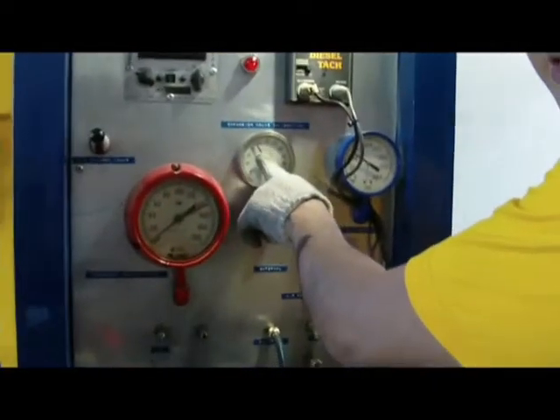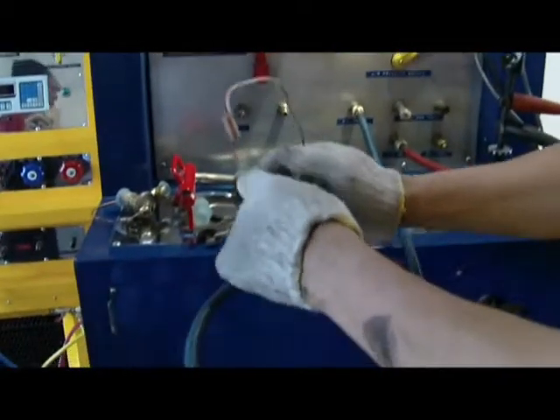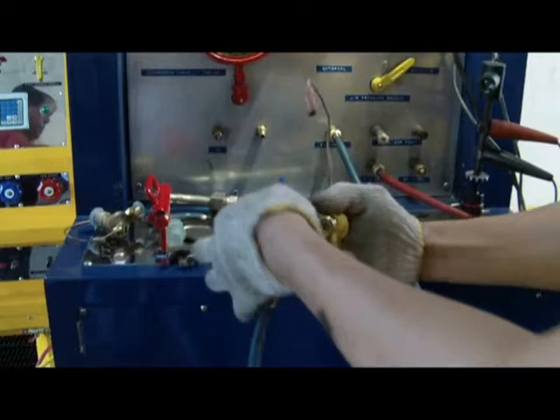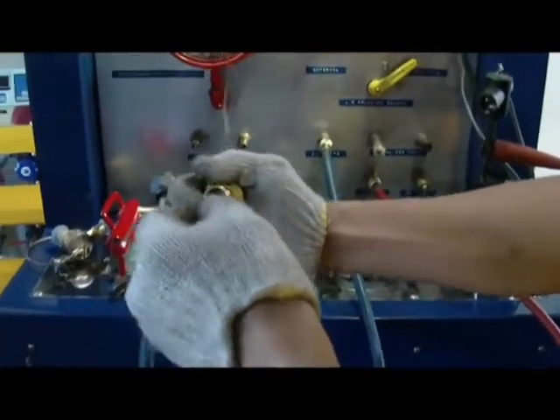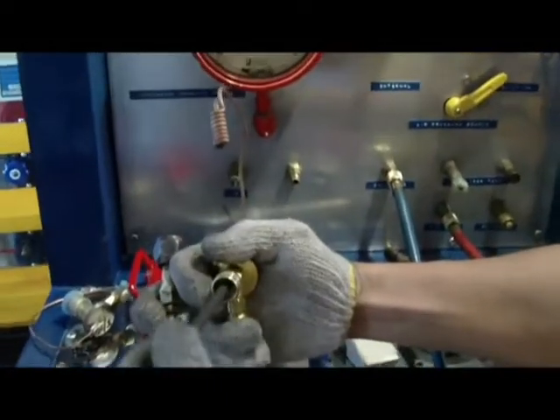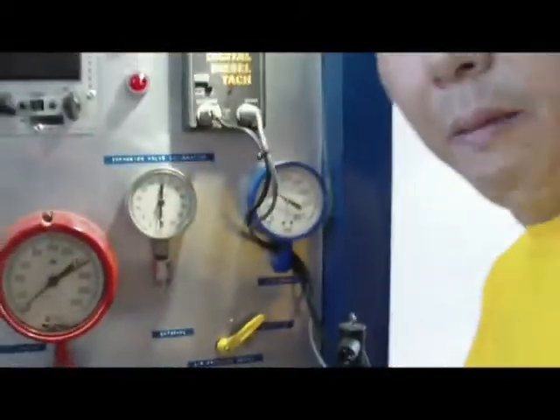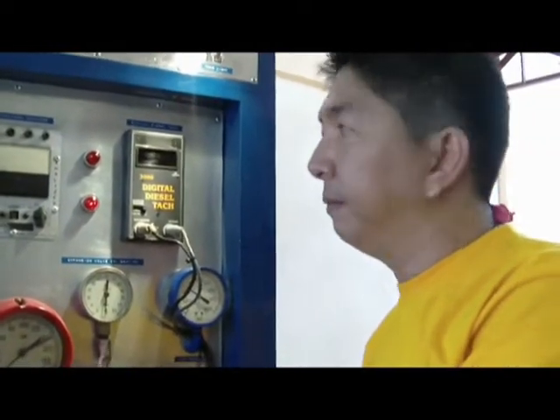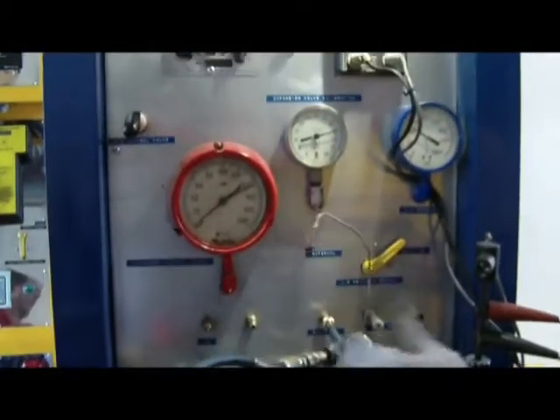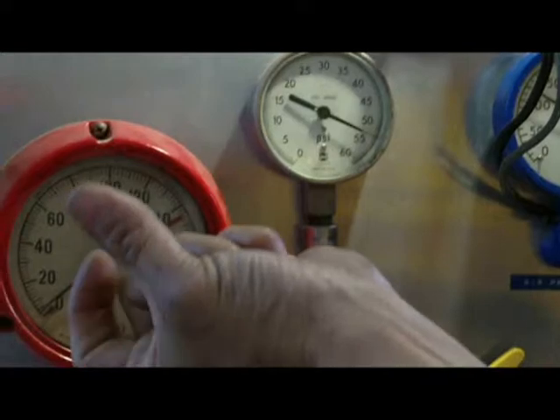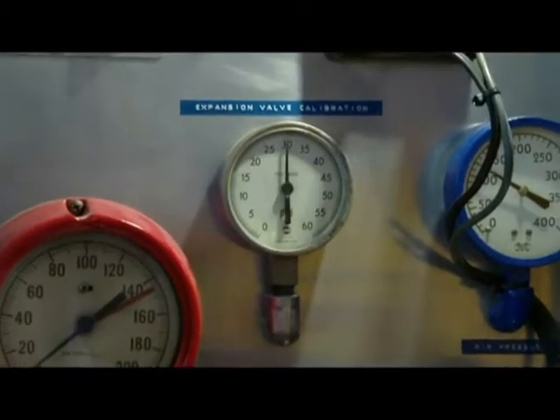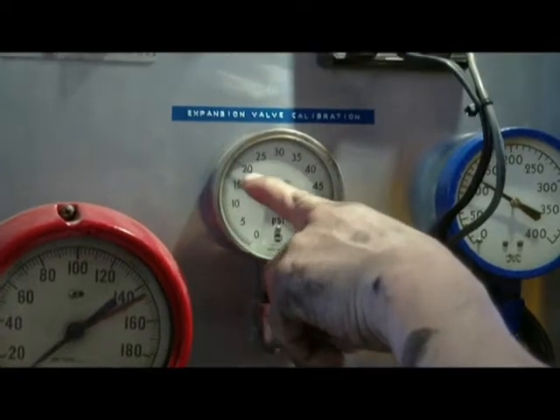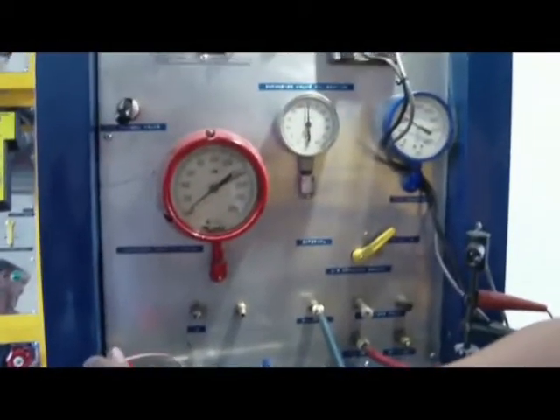So in this case, if I want it to be a little bit lower, I need to move it clockwise. As you can see the hole here, I can adjust it to a little bit lower stage. Whatever setting I want, I can make it because I have this expansion valve calibrator that I invented for this expansion valve. You see, it will go higher once it feels hot, and it will go lower once it feels cold. You can even see the reading here because I've adjusted it. And once the ice is removed here, it will get higher again.